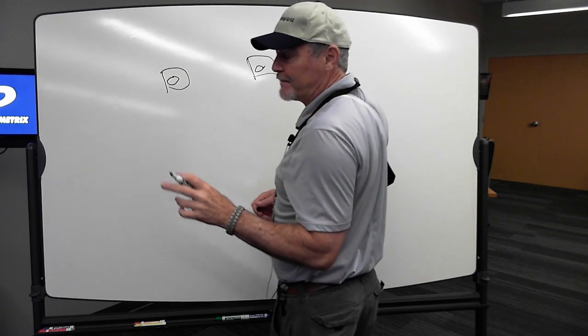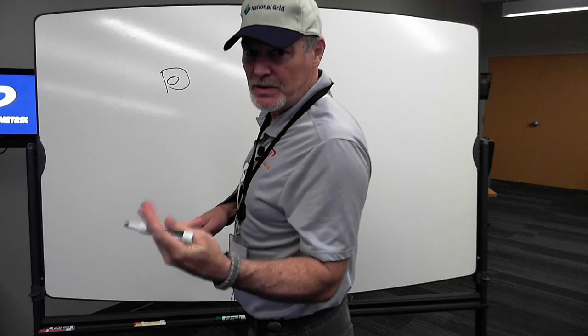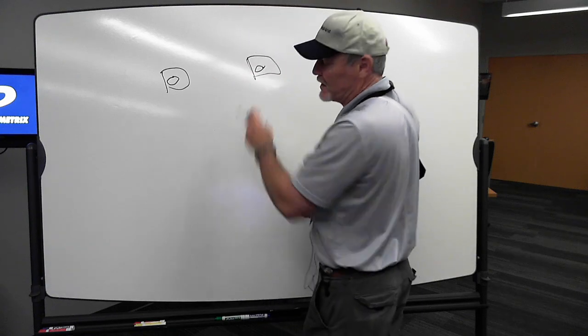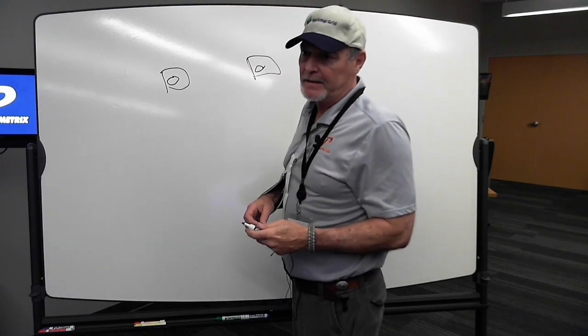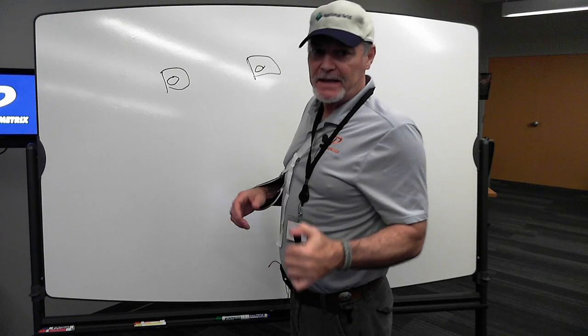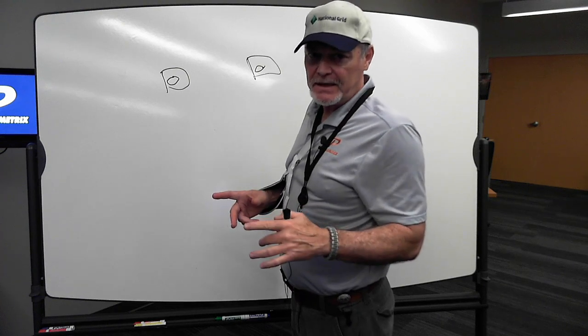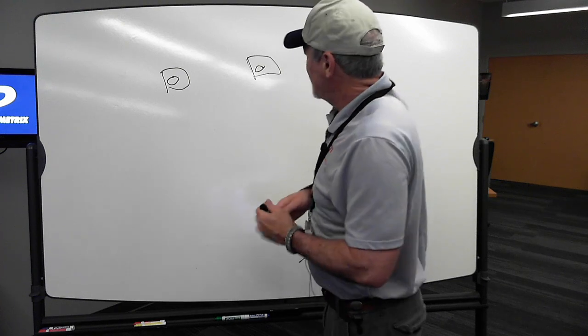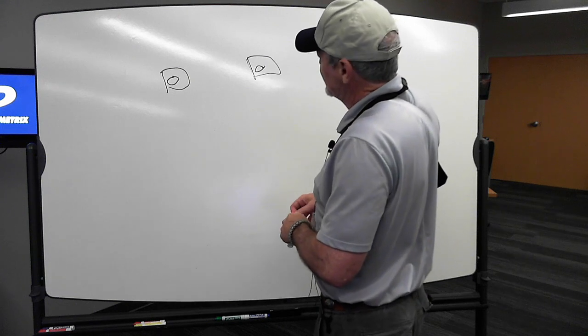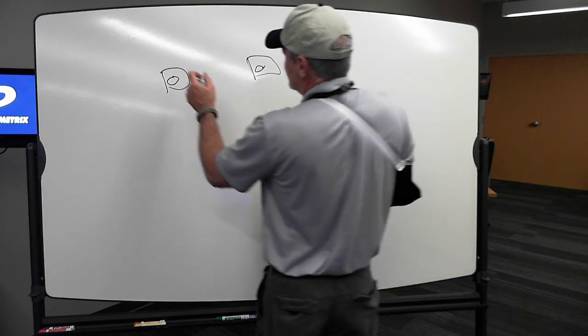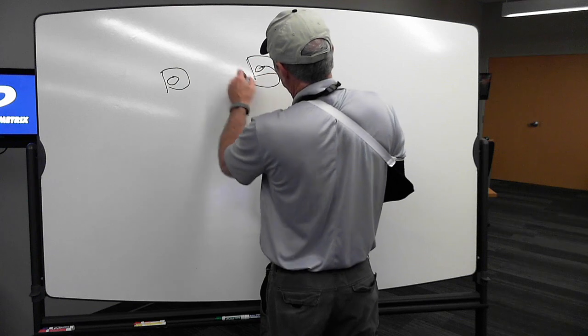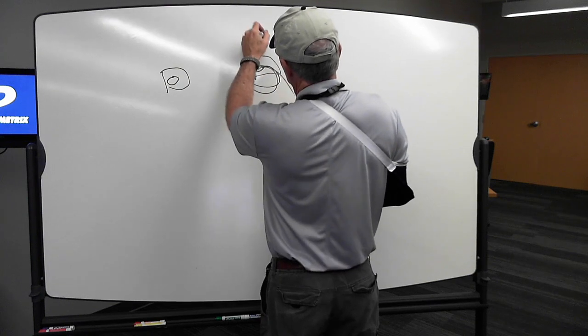We were saying I've got 3 voltages, but only 2 currents because I've only got 2 CTs. You'll hear this a lot over the years, where they say we're trying to save money using only 2 CTs instead of 3. The bottom line for you and I on the testing is what they've done is loop through the 480 side over here.